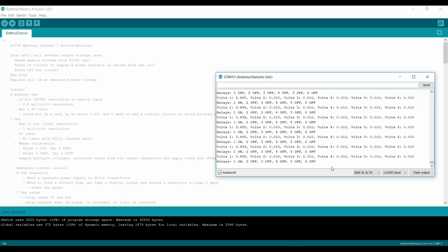Now I'm not draining this particular cell because I'm only reading it across the analog input. It's not in the circuit with the resistor. But I'm going to take the wire off the battery. Click, battery goes off, and we're floating down to a low voltage level, and the relay is off. And we go on again and off. So functionally, the circuit works except for reading the individual battery levels.